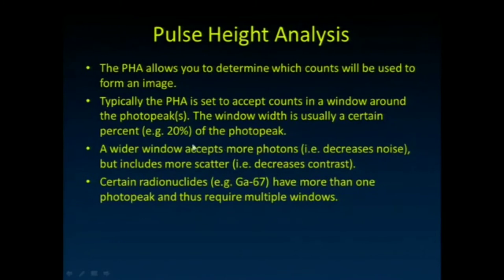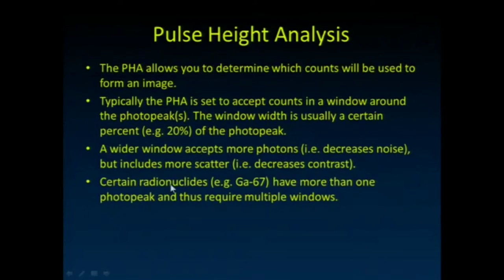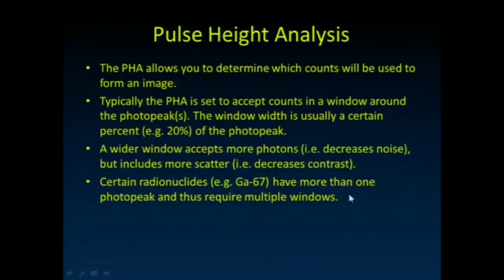A wider window would accept more photons and decrease noise, but scattered gamma rays — which have lower energy — would also be accepted, degrading image quality. Certain radionuclides like gallium-67 have more than one photo peak; they emit gamma rays of multiple different energies. For those, we set up multiple narrow acceptance windows centered right at each peak, rather than one wide window that accepts everything between them.